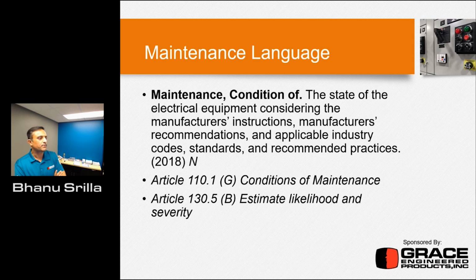Okay. So if you look at the maintenance language from NFPA 70E 2018 edition, there's one definition that's been added. It's called "maintenance condition of." This is the state of electrical equipment considering the manufacturer's instructions, manufacturer's recommendations, and applicable industry codes, standards, and recommended practices. If one dissects this specific language, what it's saying is you need to follow the manufacturer guidelines or instructions when you're performing these maintenance tasks, right? You need to go back to the instruction manuals or installation guidelines provided by those manufacturers on their scheduled maintenance activities for that specific equipment, right?